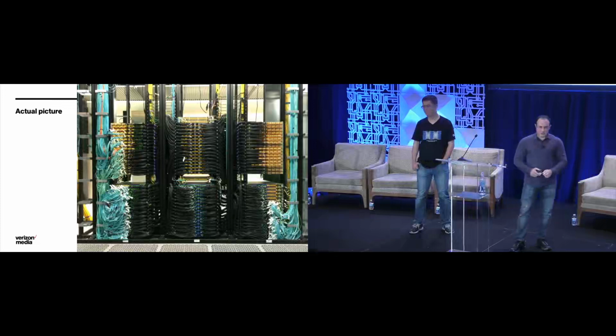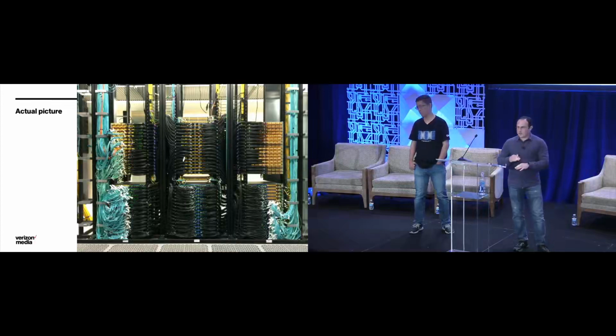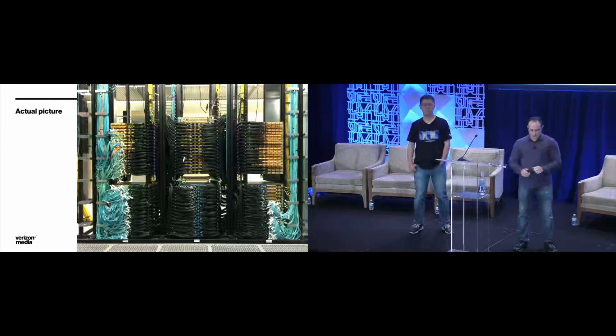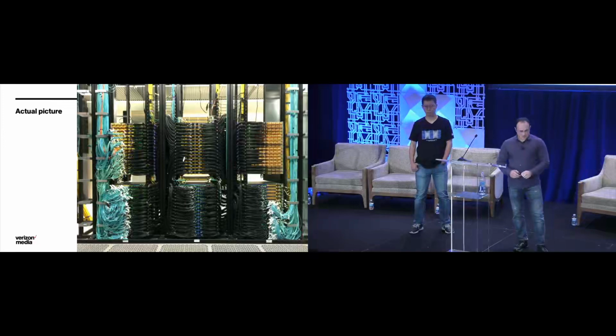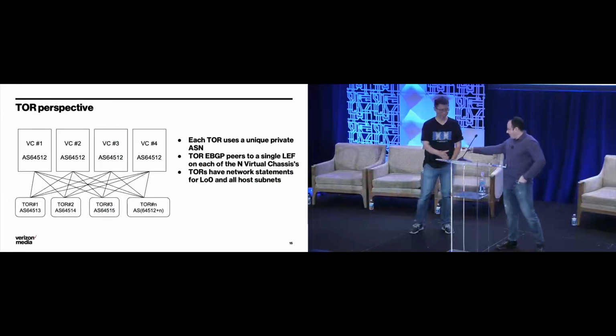Also, we had to custom design the racks and cable management for handling 2 tons of cable on each side, and also making sure that this much cable, when it lays on each other, doesn't actually crush itself, because that could have happened and has happened when we didn't use these things. Now, for the routing topology of how it is, over to you.